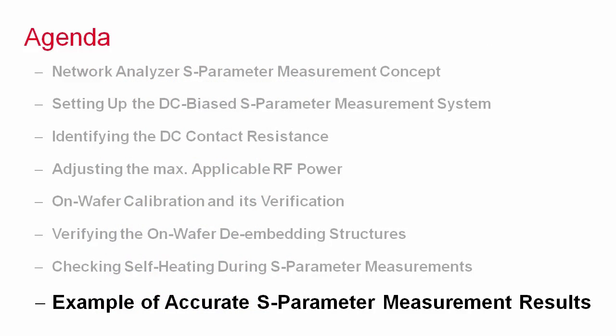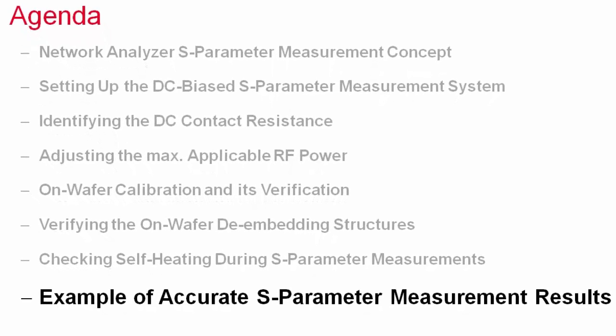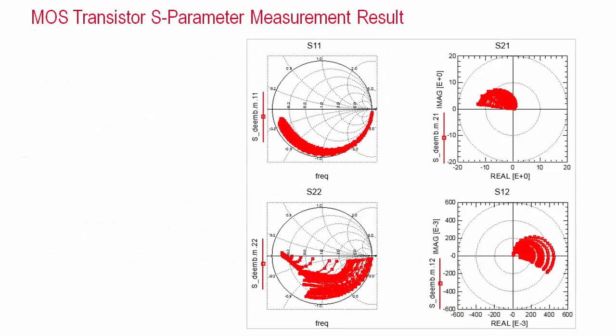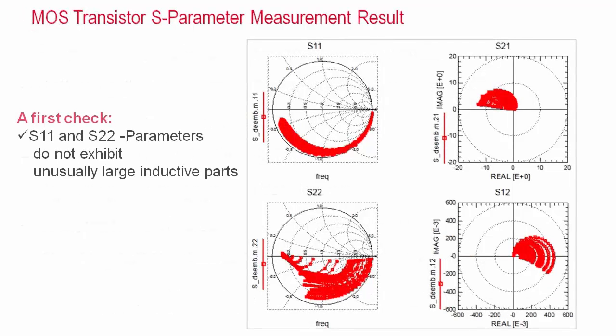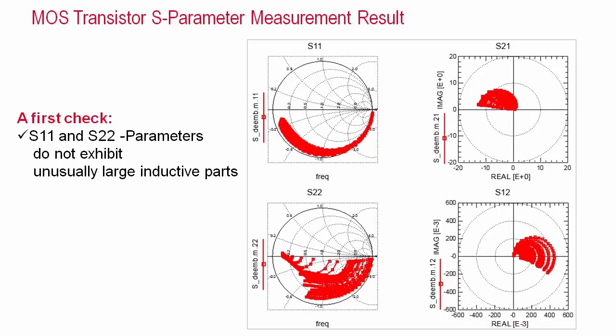With all these prerequisites fulfilled, everything is now set up to perform accurate S-parameter measurements. Let me show you an example of a MOS transistor. A first check is the behavior of the high frequency endpoints of the S-parameters. In our example, a measurement directly on the wafer does not assume large inductances, and the traces of S11 and S22 are not extending into the inductive half-plane of their Smith charts. So that's okay.